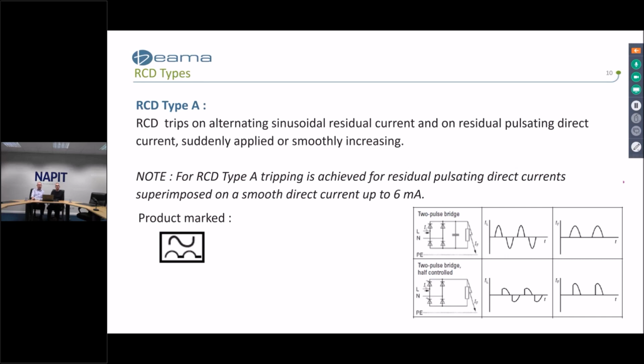The next RCD type to look at is Type A. This type is also common within the UK and has been available for many years. Type A RCDs will respond to alternating residual currents, just like the AC, but also to pulsating direct currents. This may be loads with electronic switching, such that chopped wave fault currents can be produced. An additional aspect of Type A RCDs is their ability to continue to operate when there's a superimposed direct current of up to 6 milliamps.